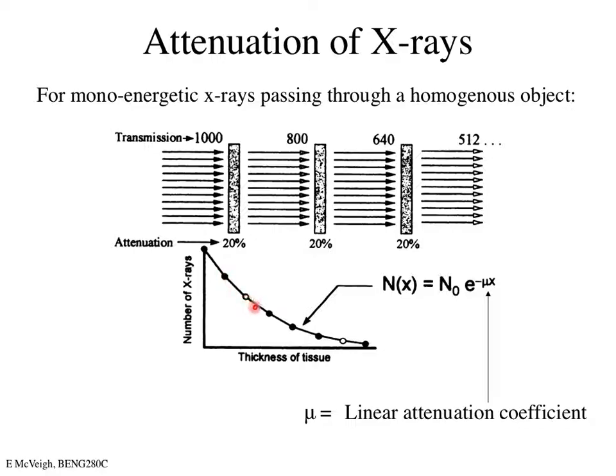The linear attenuation coefficient mu characterizes the interaction of x-rays with the material. Water has a specific mu — requiring many centimeters to reduce x-rays by 50%. Bone has a much higher mu — far less distance is needed to attenuate x-rays by 50%. The image we display will be a map of mu as a function of position, with brightness linearly proportional to the value of mu at each point.